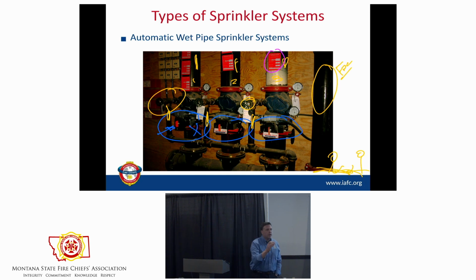Okay, right, typically our newer big box, all of those without fire pumps, it's about 150, right? If you're downtown Butte and that sprinkler system's older than God, like it's a 100-year-old system, I'm not pumping that at 150 unless I absolutely have to, right? I'm going to bring it up. Now think about this. How many have pumped into an FDC at a working fire?